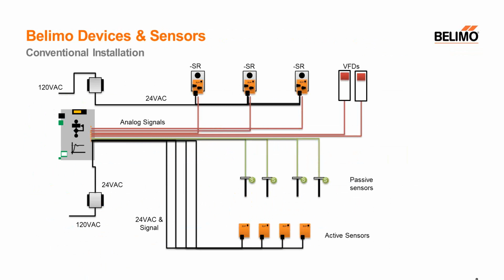Here's what the wiring kind of looks like. On the left, you have a programmable controller, and then you have analog signals, basically a 2 to 10 volt signal or a 0 to 10 volt signal, connecting individually to each of the actuators. If there are VFDs on the project or on the air handler, they tell the fans what speed to run at. You have connections for passive sensors to sense temperatures, and then active sensors which produce a voltage or a current to represent things like humidity and pressure. So lots of home runs between this digital controller to connect to outputs and to connect to inputs.